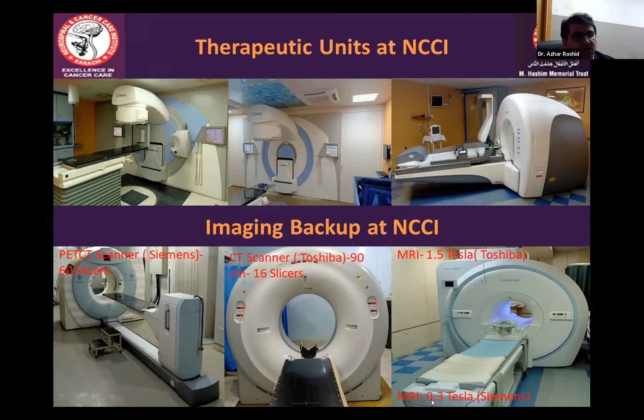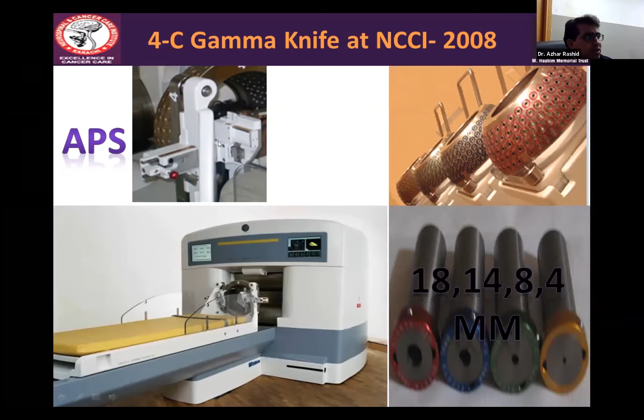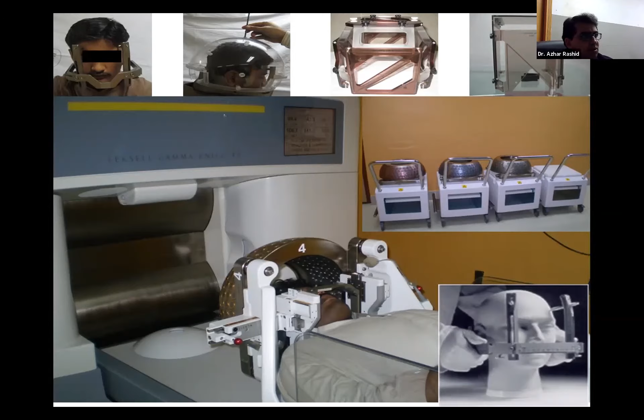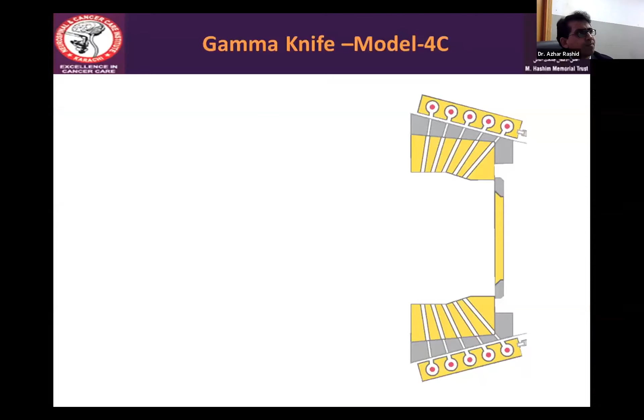This is the 4C model, which initially came to Pakistan, and this model had manual collimators. These were helmet-shaped collimators having 4, 8, 14, and 18 millimeter bores. You can see the collimator sizes, and these were the trolleys carrying the helmets, which were manually loaded into the system at that point. This is the MR localizer, this is the CT localizer, and this is a trolley. That trolley had to be manually pushed towards this machine, and it was loaded automatically, but it took a long time to change over different collimators, particularly for lesions which were small and close to the brainstem or close to the optic chiasm. We needed smaller collimators, and that is what took a long time to treat the patient.